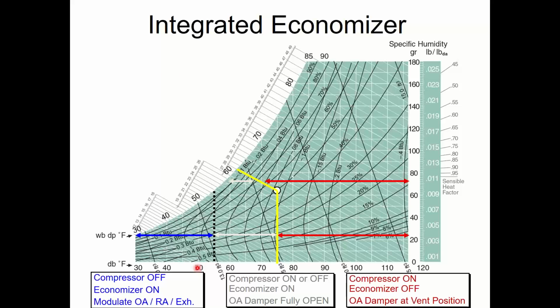Essentially what's going to happen is the economizer is going to become stage 1 and the compressor is going to become stage 2. That is why you must, I repeat, you must always have a 2-stage thermostat for all commercial systems. Even if you only have 1 stage of compression, you still got to buy a 2-stage and wire a 2-stage thermostat. Because when I have an economizer, if it's nice outside, stage 1, Y1 off the thermostat, becomes my first stage of cooling. And Y2 off the thermostat, stage 2, becomes my compressor. So I always got to have a 2-stage stat on an economizer system.